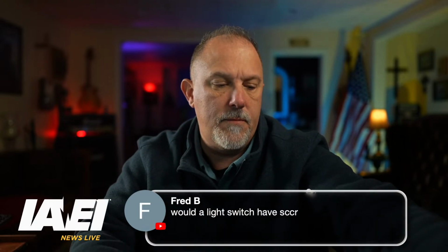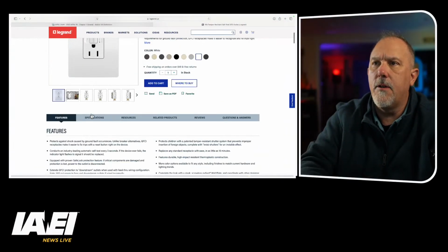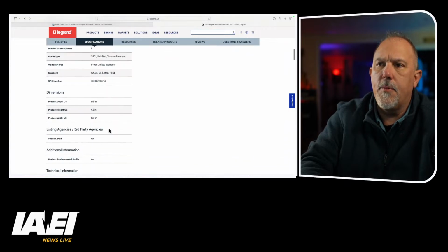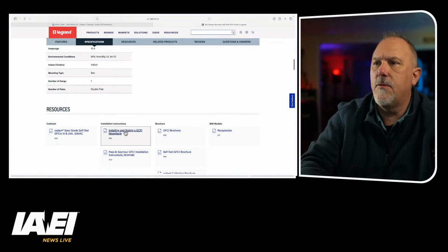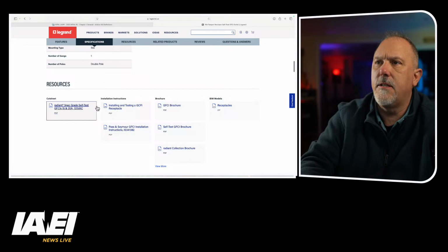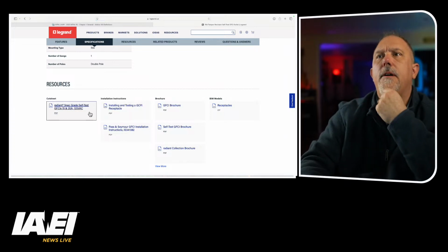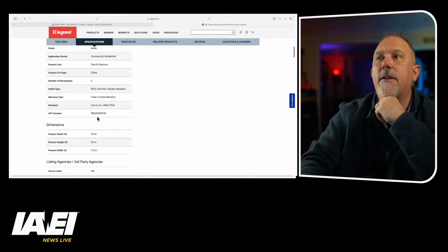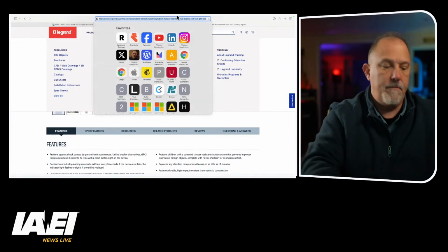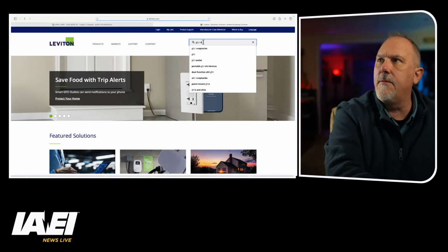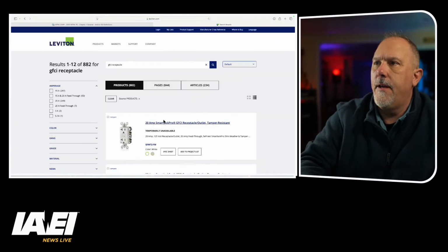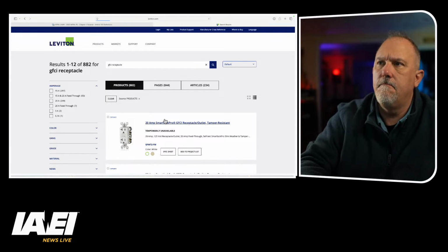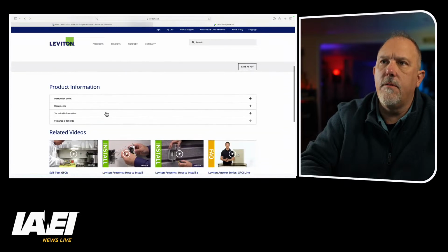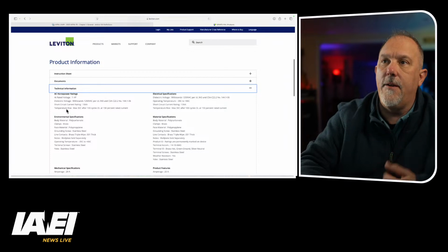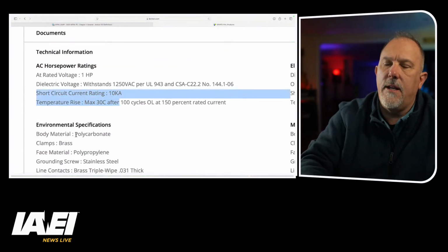Okay, so now I'm just going to take a look at the receptacle. I'm going to go to specifications, product dimensions, resources, test guide, installation. I'm not seeing it. There should be a short circuit current rating on here as well. Let's go to Leviton. Let's take a look at a GFCI receptacle. And let's just look at one of these. And we scroll down, instruction, documents, technical information. Hello. There we go. Look at that. Short circuit current rating is 10,000 amps on this receptacle.